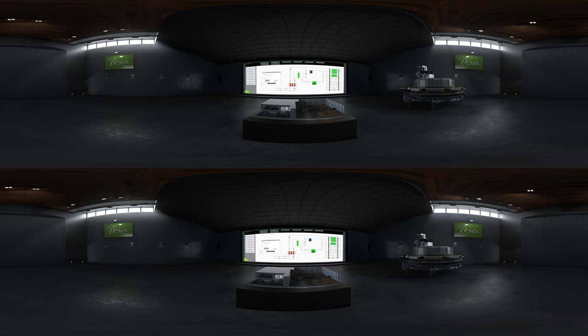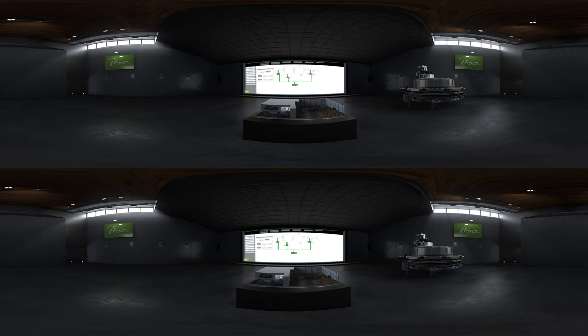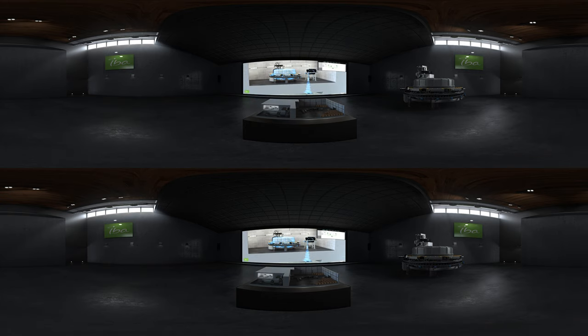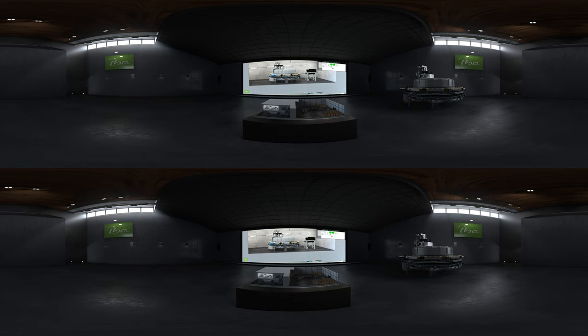Now switch the vacuum system on. The vacuum on the cavity and the beamline is the first one to be activated. Rotary and turbo molecular pumps remove the air inside of the machine and its components, including the beamline, to reach a high vacuum level. The same is done with the electron gun. This will remove the molecules of air that could generate collisions on the electron path.